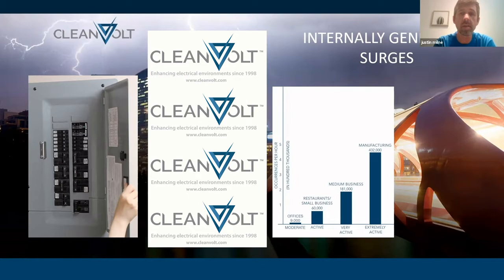So I know these numbers seem rather high, but you have to keep in mind that compared to 20 years ago, we're utilizing a lot more electronics when it comes to our automation and our efficiency strategies. And these electronics by nature create harmonics, deviate the voltage waveform, and cause energy surges to be created.